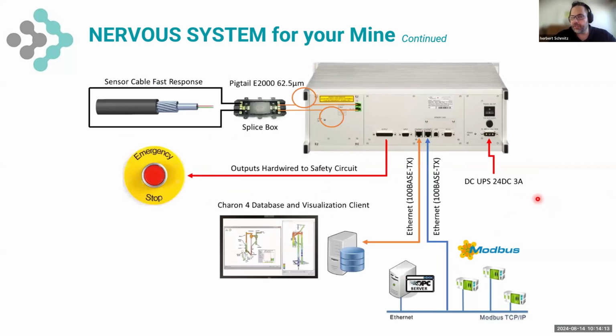This is a typical connection installation. This is a 2-channel system. We can have up to 4 channels on the fire certification. If fire certification is not important, we can have up to 16 channels. In most safety applications, we do install in a loop configuration. It could also be installed single-ended.